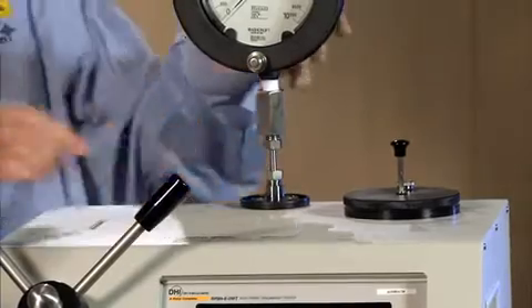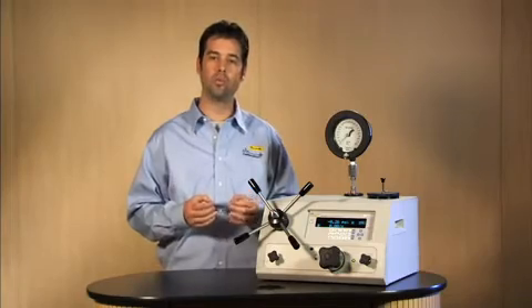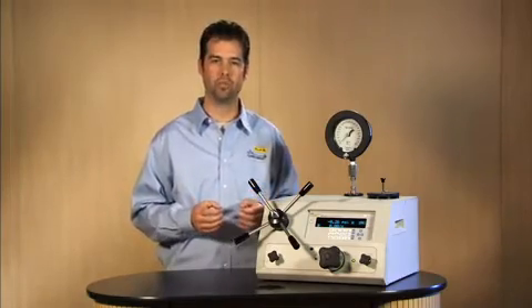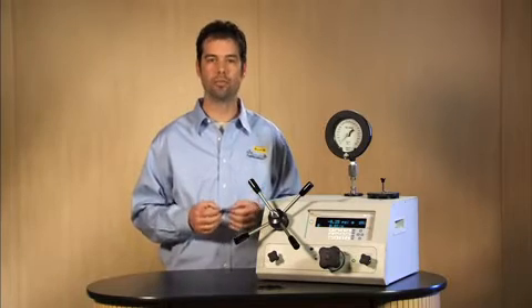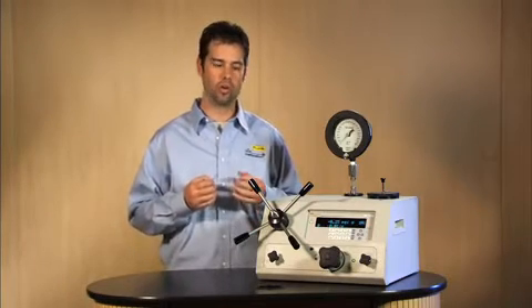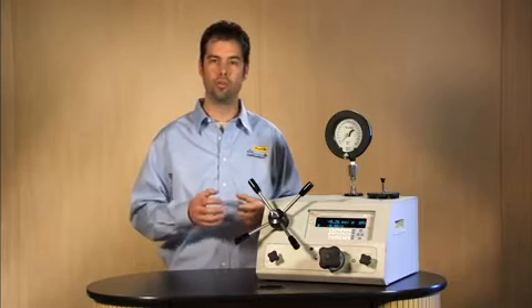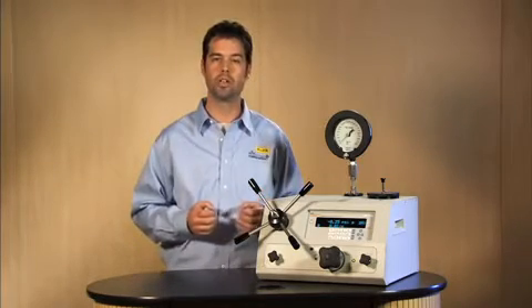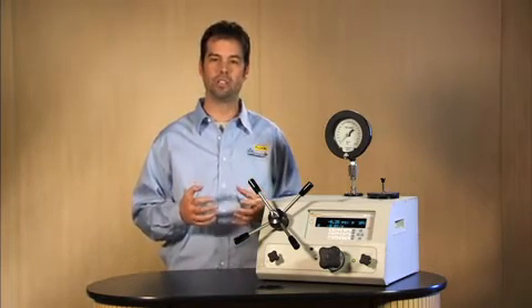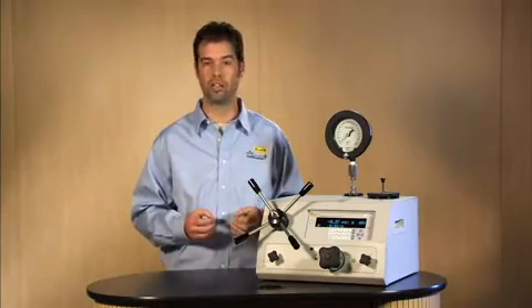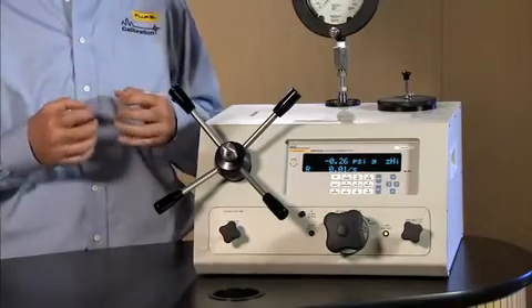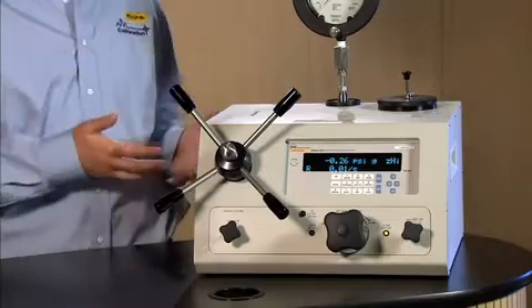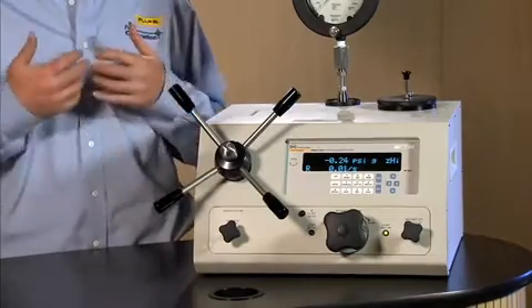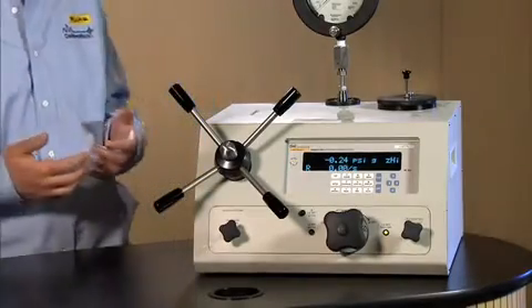Now we need to make sure that we don't have any gas in the system. Gas is a very compressible fluid, so when you use a variable volume type of system, the more gas you have in the system, the more gas that you will have to compress. It's to your best interest to remove as much gas as possible. Well, the electronic deadweight tester has a feature to help in that process.